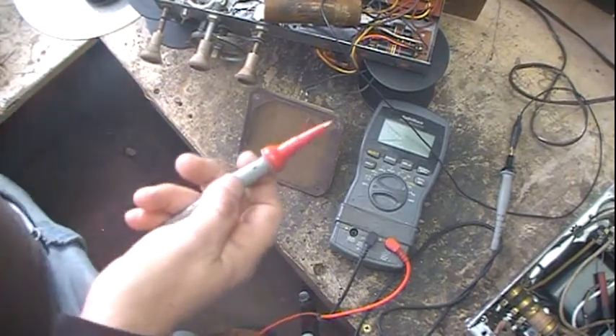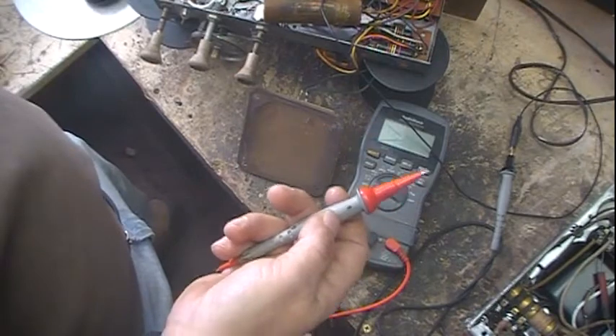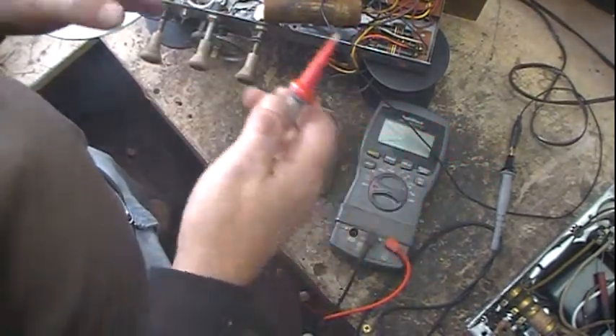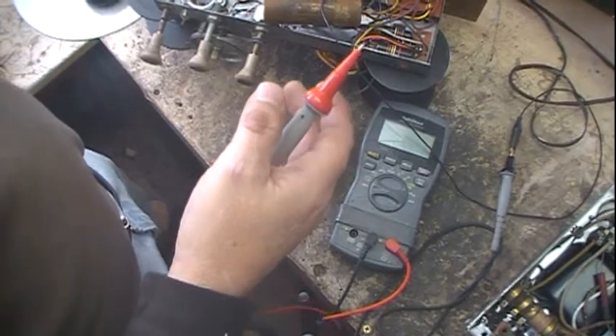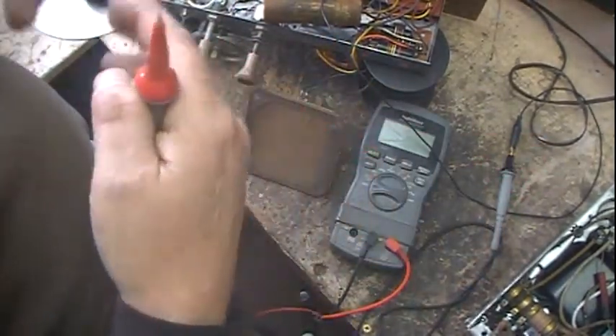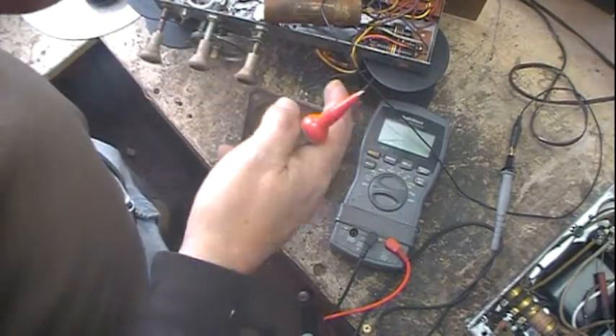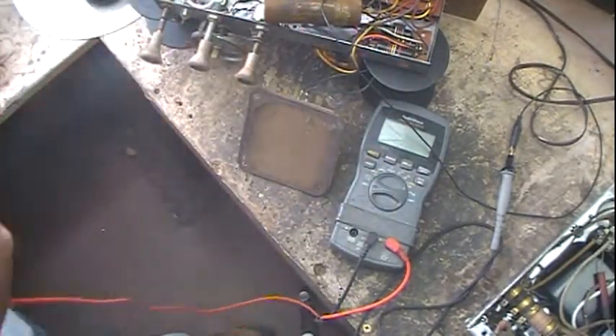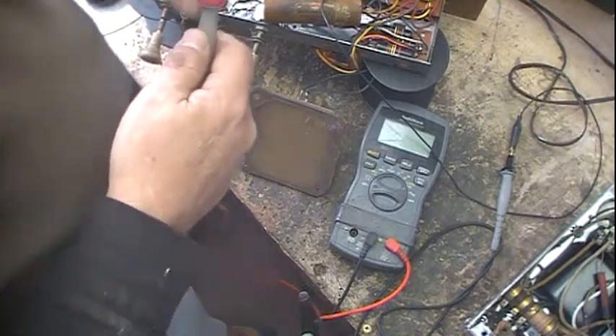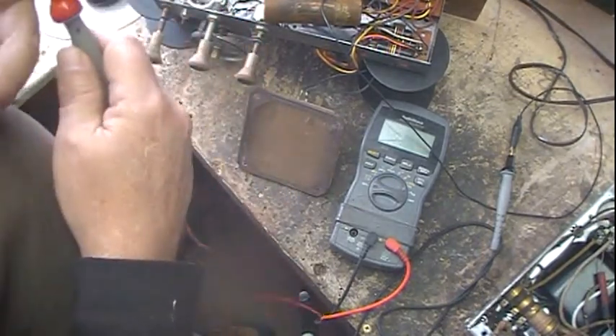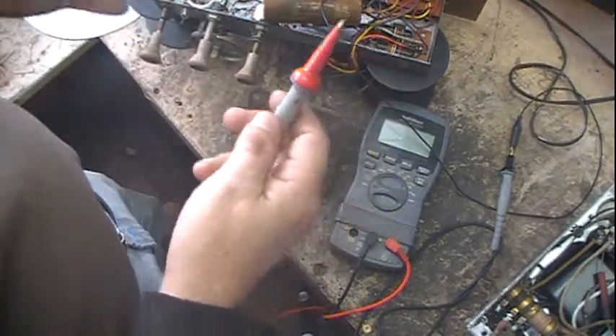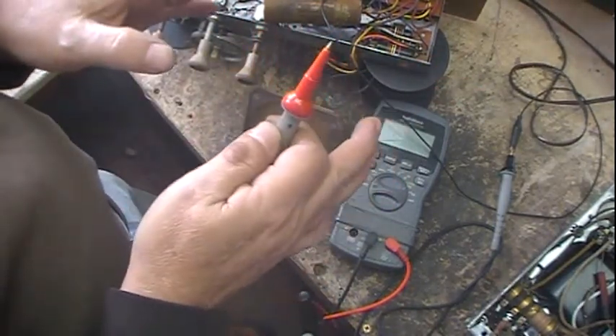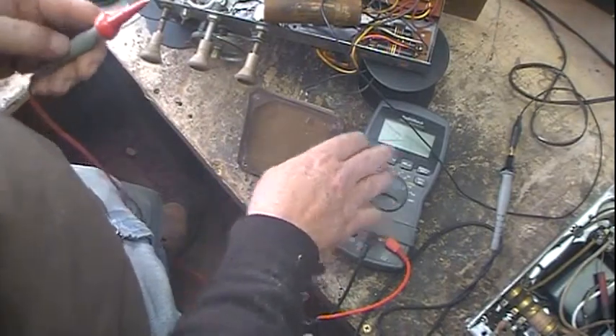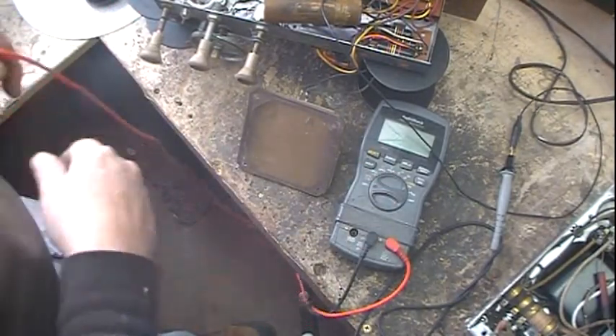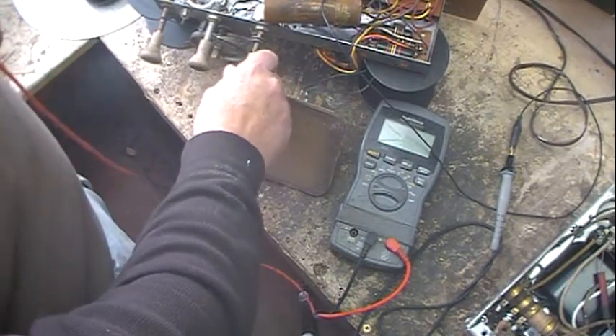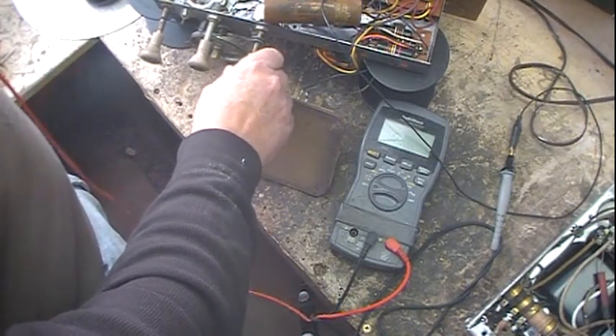The nice thing about the continuity tester is that it makes a noise, so when there is continuity, the wire's good, or you found the correct end, you get a beep. You don't have to look at the meter. You could do this with resistance, but you'd have to watch the meter. Everything else, coils, transformer windings, IF transformers, power transformers, anything, those use resistance measurement. Check the ohmage.